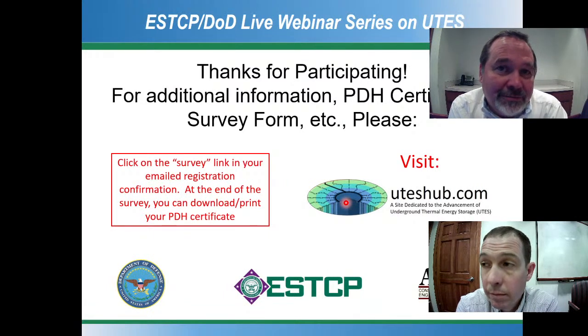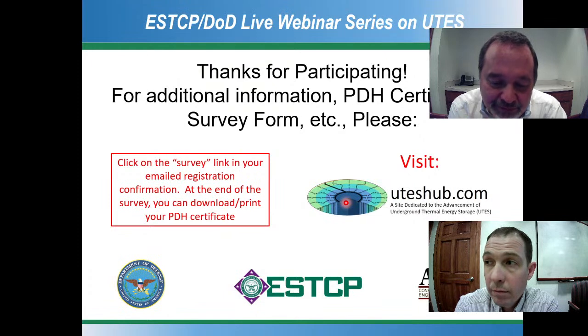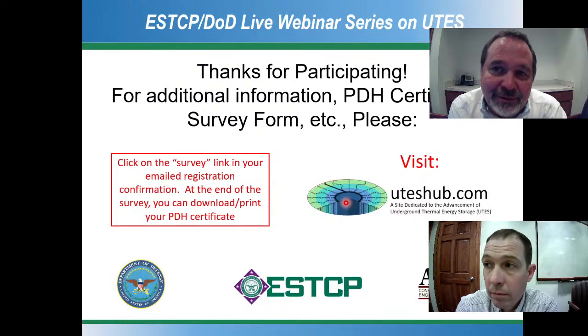Right, yeah. And on the open loop systems, ATES, a traditional system will have dedicated supply wells and then dedicated injection wells that will ideally have the injection valve like we showed, because you want to keep back pressure on the system at all times, and you really have to put that valve at the bottom of the injection pipe, down deep underwater. We don't want to mix oxic water with anoxic water. We don't want to get oxygen in the system. Some critical things there are to keep those systems under pressure so you're not mixing water flow, and to make sure those injection valves are operating properly. As Brandon alluded to, we've had a couple of problems where we weren't getting even flow through the injection wells.